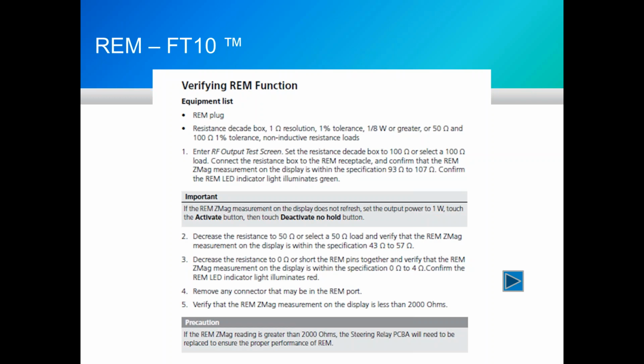The REM test on the FT10 we do not do in clinical mode, but we go into the service mode, and we're going to use 4 set values. We're going to test at 100 ohms, we're going to test at 50 ohms, we're going to test at 0 ohm or short circuit, and we're going to do a test with that port open or infinity.